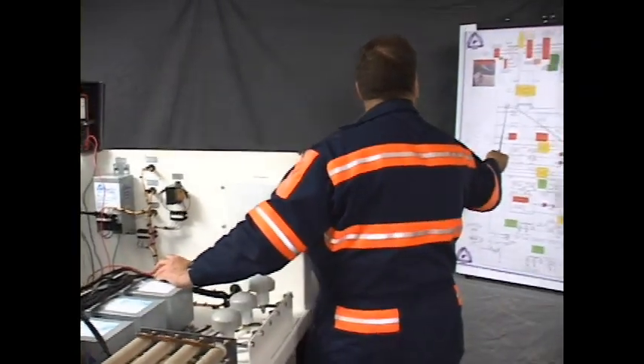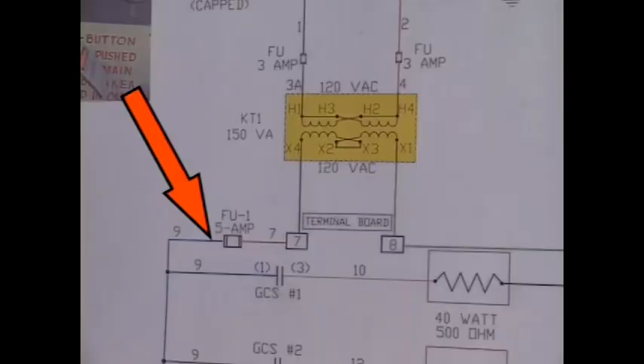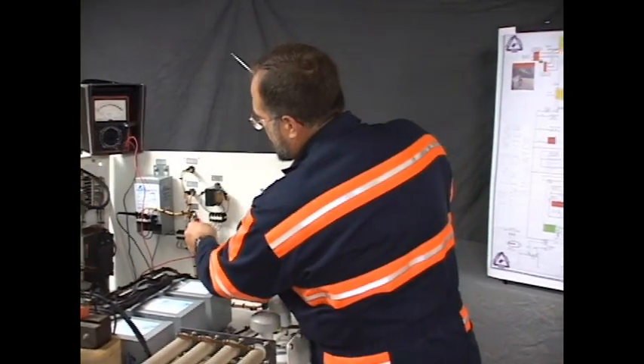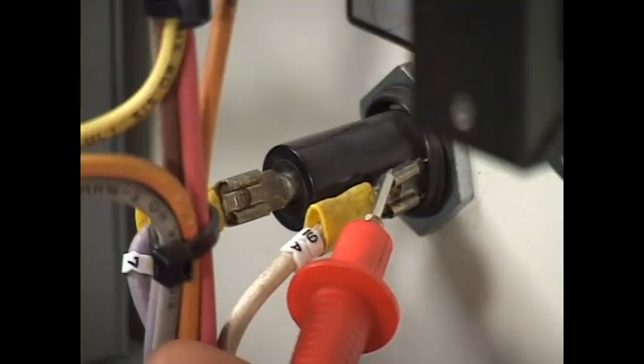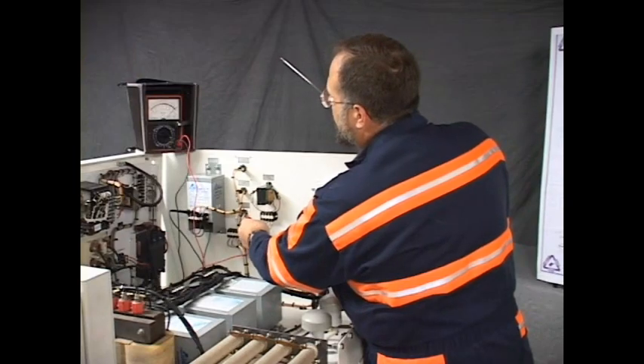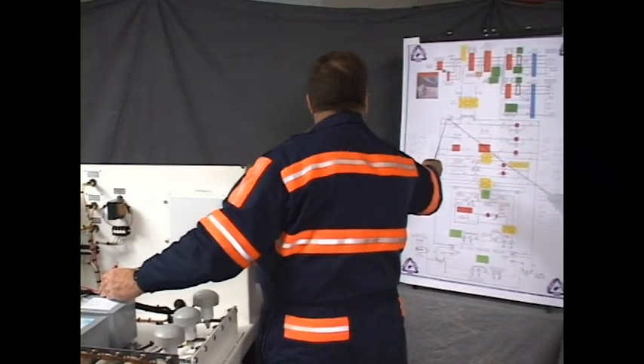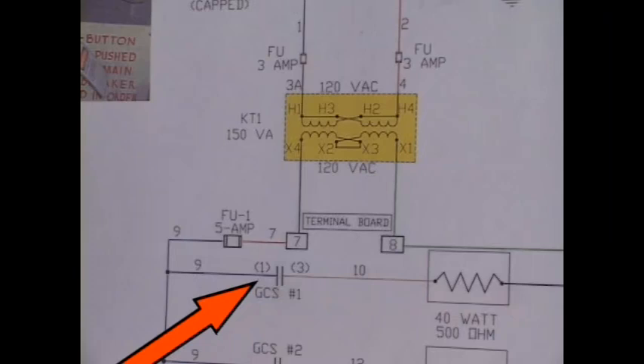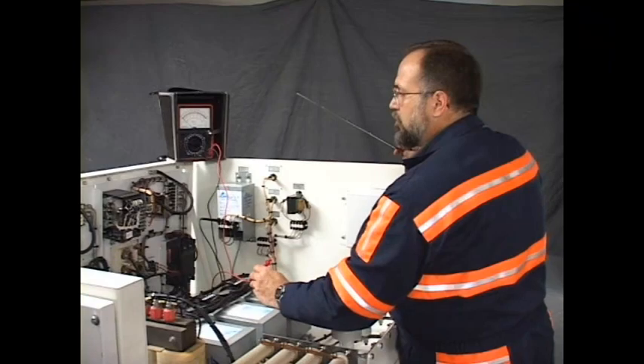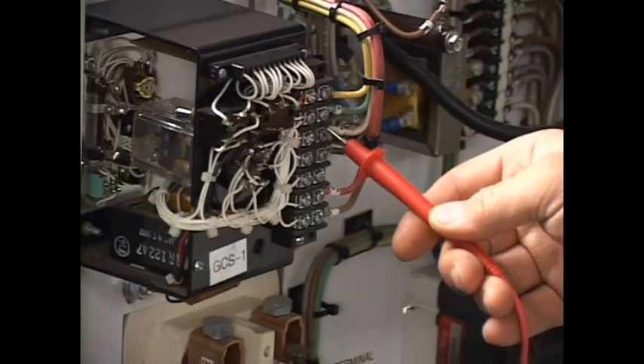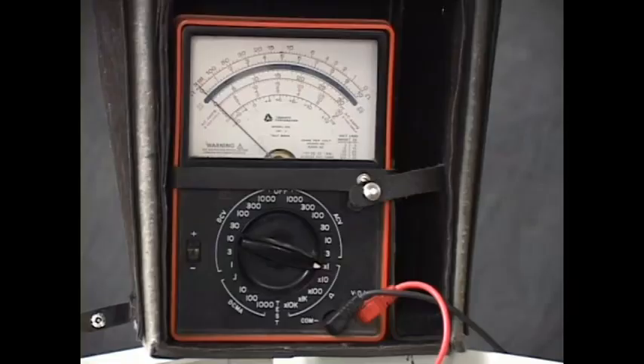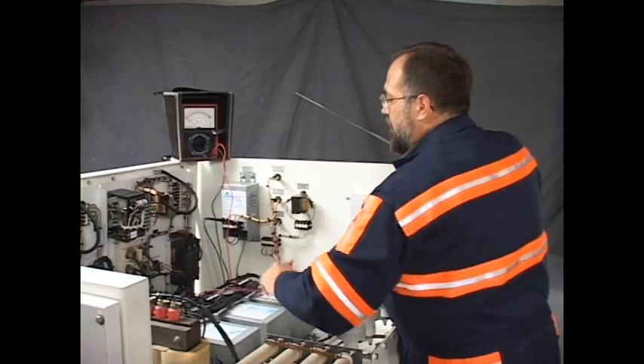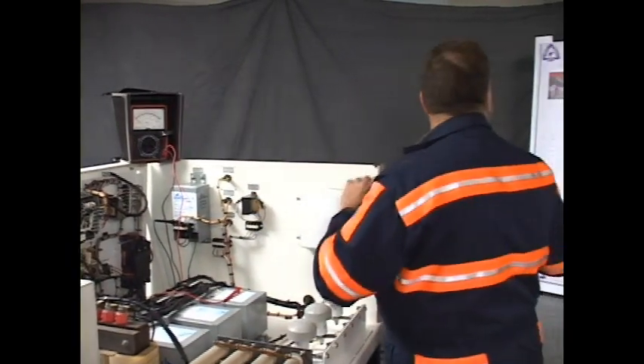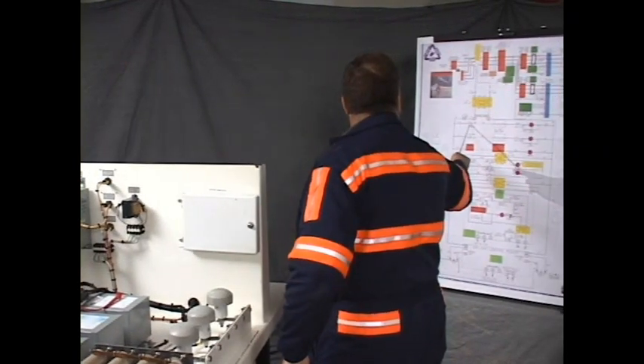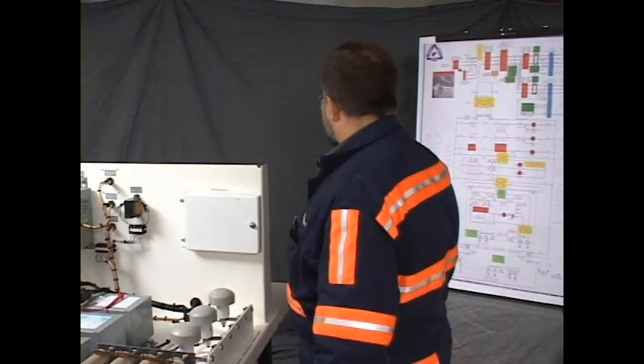The next point would be through the fuse to the load side of FU1. This checks the fuse as well as the fuse holder, and it's good, no resistance there. The next point that we can access would be terminal 1 of GCS1. This is GCS1, ground check system number 1, the next rung of the ladder. And we read to there. Whoa, we have an open circuit. Wire number 9 is broken between the load side of FU1 and the terminal 1 of GCS1.